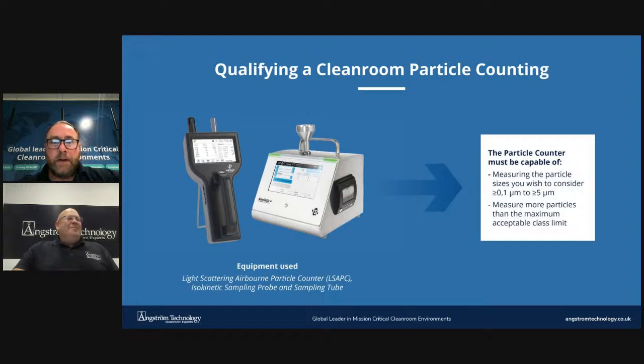To perform particle counting, we would use a light scattering airborne particle counter, or LSAPC for short, usually a handheld or a portable, as per the two devices shown on screen. These devices would be attached to an isokinetic probe with some sampling tube. A tripod may be used for support. So the isokinetic probe is determined by the particle counter's flow rate, and the sampling tube should be kept to a minimum length. The particle counter must be capable of measuring the particle sizes you are wanting to consider, and must also be able to measure more particles than the maximum limit of the class.